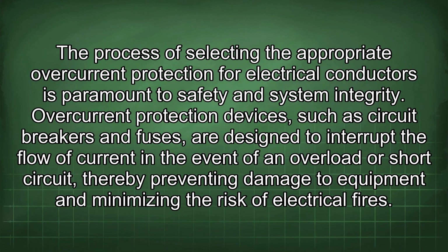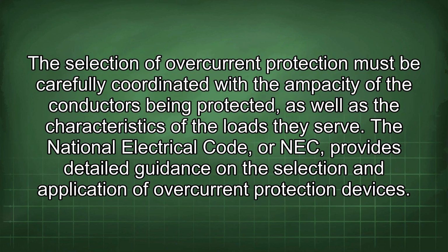The process of selecting the appropriate overcurrent protection for electrical conductors is paramount to safety and system integrity. Overcurrent protection devices, such as circuit breakers and fuses, are designed to interrupt the flow of current in the event of an overload or short circuit, thereby preventing damage to equipment and minimizing the risk of electrical fires. The selection of overcurrent protection must be carefully coordinated with the ampacity of the conductors being protected, as well as the characteristics of the loads they serve.